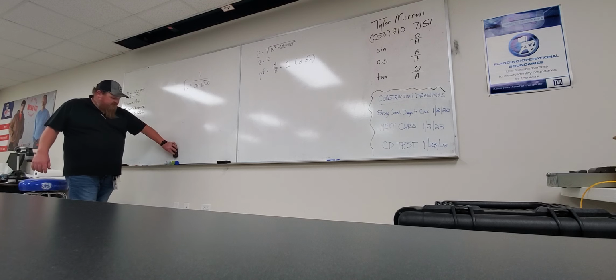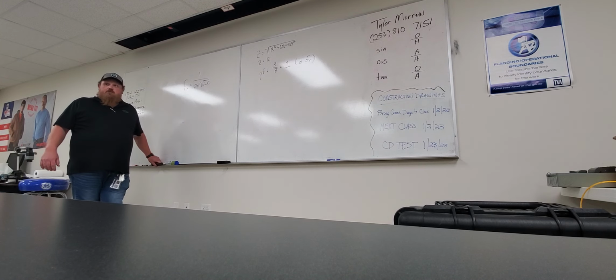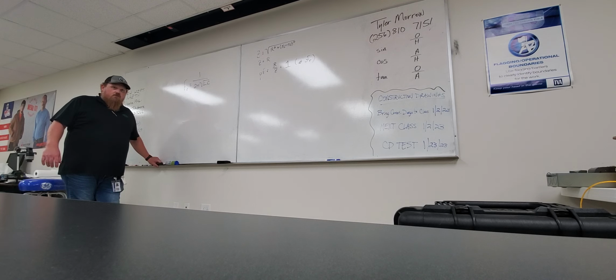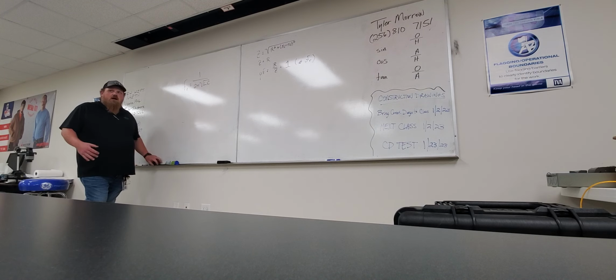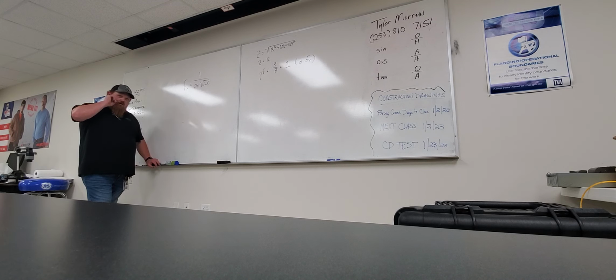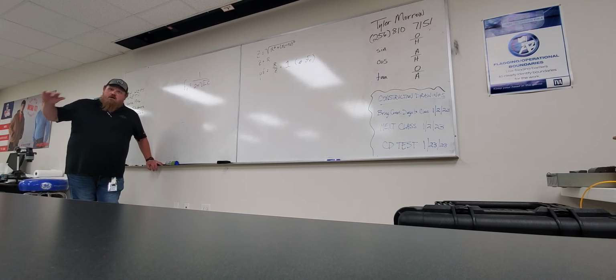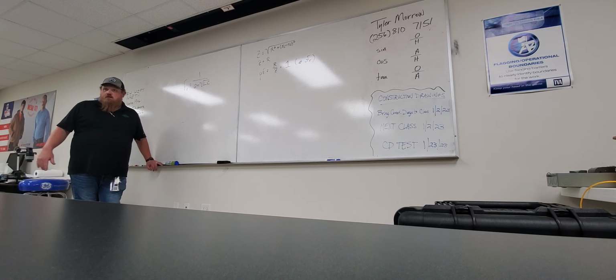Not only is it efficient as far as the power bill, places will actually get fined if their power factor drops to a certain point. They start getting fined until they get it corrected. And that's some of the problems we go through: you need to drop the inductance down a certain amount. How many capacitor banks will it take to do it? The capacitor banks cost X amount. How long will it take for them to make their money back? That type of thing, right?